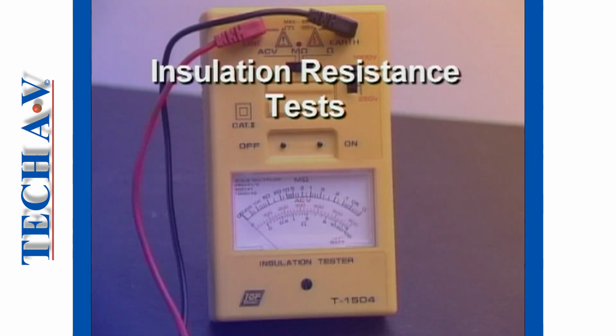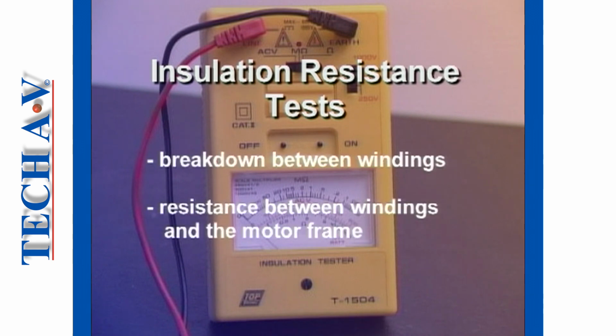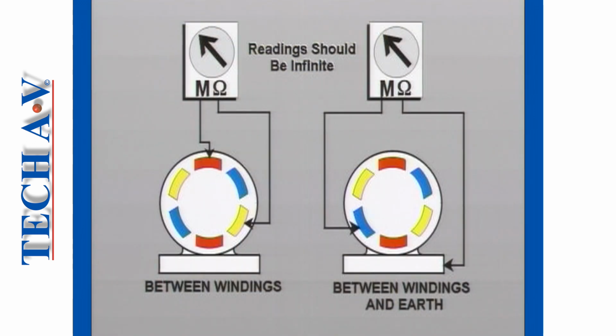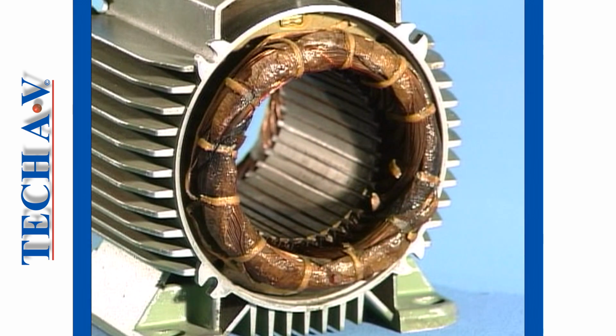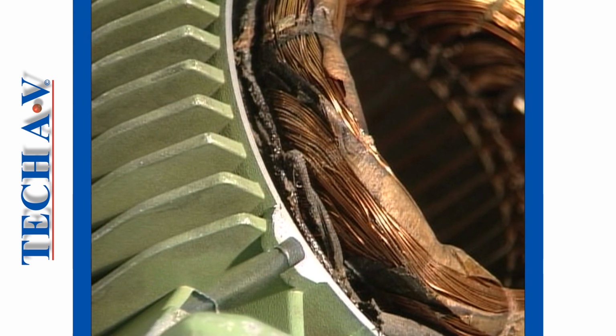Now we move on to the insulation resistance testing procedures, and we shall discuss how to test for a breakdown in the insulation resistance between the windings, and test the insulation resistance between each winding and the frame of the motor. Ideally, the insulation resistance between each winding and between each winding and the frame should be infinite. Sometimes, however, due to overheating or moisture within the motor, the insulation breaks down, causing a burnout.